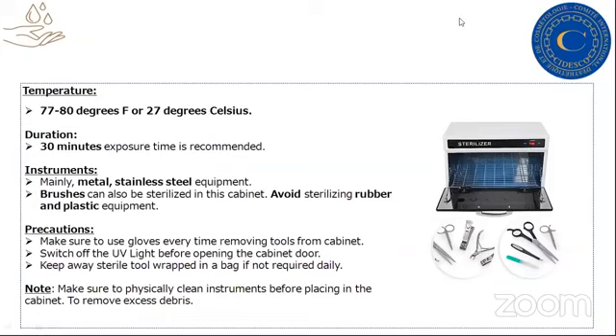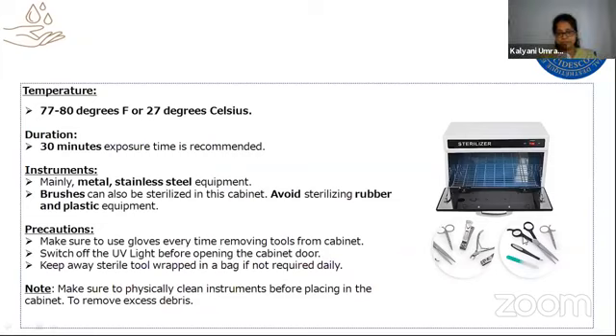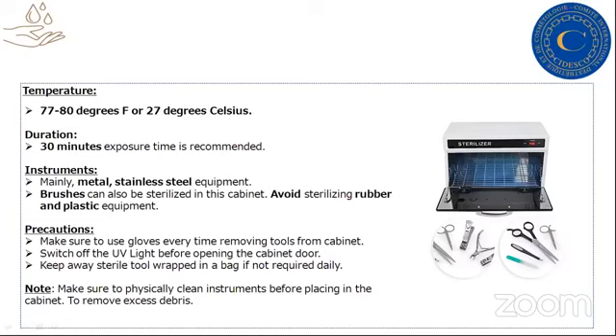Now, what all instruments can you store in that? Mainly metal, steel, stainless steel instruments. Now, brushes can also be sterilized in the cabinet. Avoid sterilizing rubber and plastic equipment. Okay, so if you put rubber or plastic equipment inside this cabinet, it's going to spoil the quality.